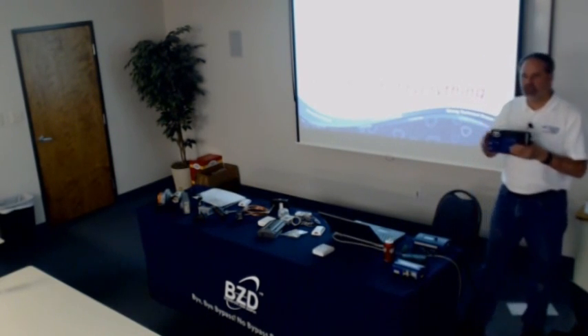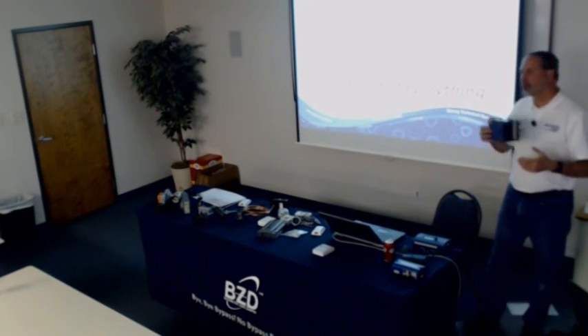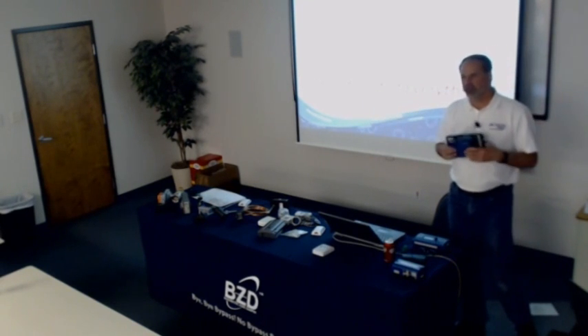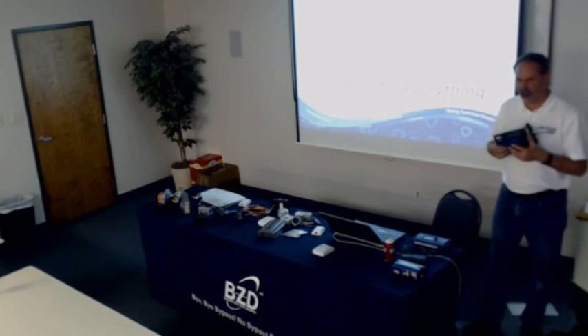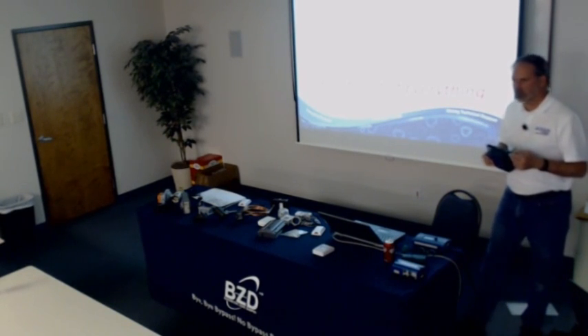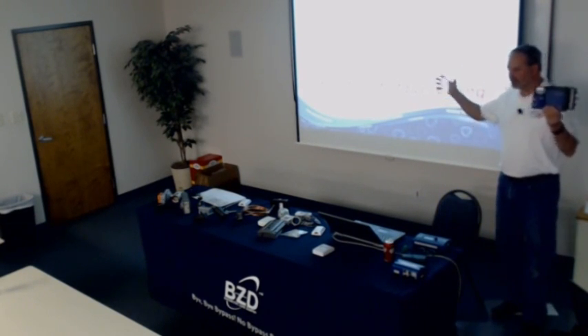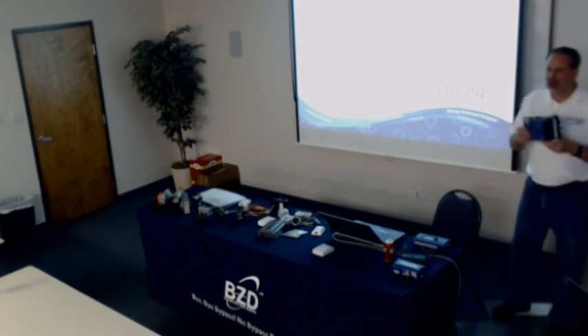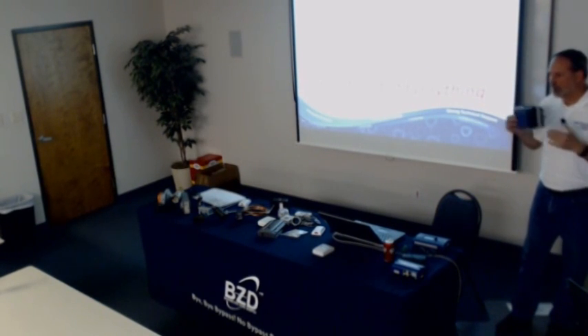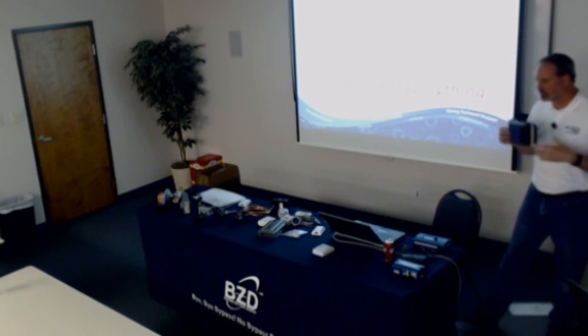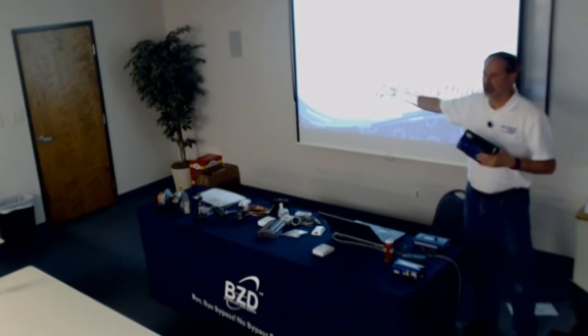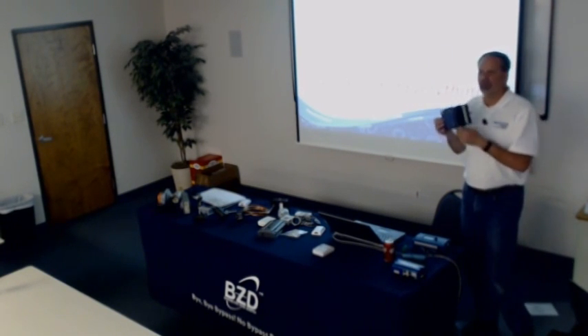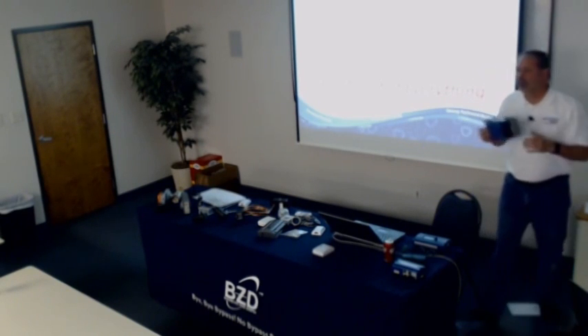And since that device is running BACnet over IP, it's actually got its own little repeater. It starts to build a mesh network with other devices. It could be another control device. It could be the building owner's wireless repeater. And if you've got an area with 10 VAV boxes up above the ceiling, all communicating over this BACnet IP network, and you have to get to the other end of the building and it's a long, long run, it's okay. You hook the BACnet wire back up and run it across the building.